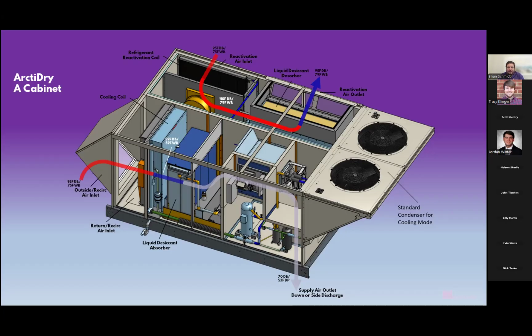So I said almost in the beginning of this presentation, there's independent temperature and humidity control. So we are not relying on manipulating temperature to control humidity. We can have cold supply air temperatures and not provide as much dehumidification if we don't want to, or we can have warmer but drier conditions. And again, that is through manipulating how much heat goes across this desorber pad, which manipulates the concentration of the desiccant. As I've said several times, the more concentrated the desiccant, the lower the vapor pressure, the higher the affinity for absorbing moisture. Again, independent temperature and humidity control.